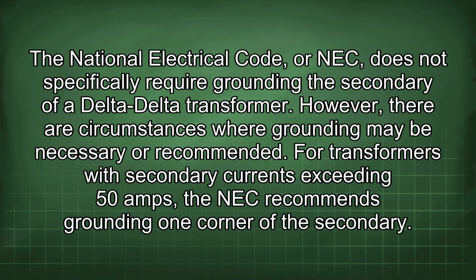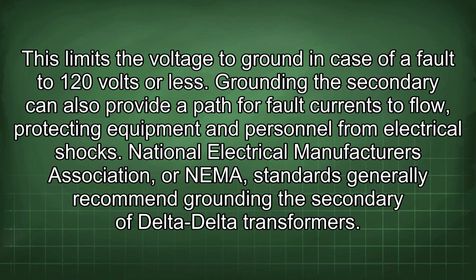The National Electrical Code, or NEC, does not specifically require grounding the secondary of a delta-delta transformer. However, there are circumstances where grounding may be necessary or recommended. For transformers with secondary currents exceeding 50 amps, the NEC recommends grounding one corner of the secondary. This limits the voltage to ground in case of a fault to 120 volts or less. Grounding the secondary can also provide a path for fault currents to flow, protecting equipment and personnel from electrical shocks.